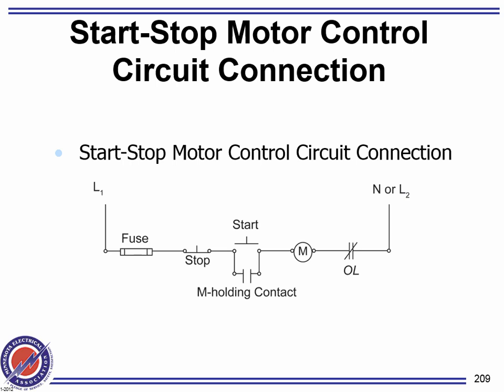Okay, so what do you need to know about that? I want you guys to pay attention to how this is drawn. See that little thing at the bottom? It must be like this. This is the start. The stop. Look where the stop is. We draw the stop. Look at the coil. The holding contact must always go across the start, not the stop.